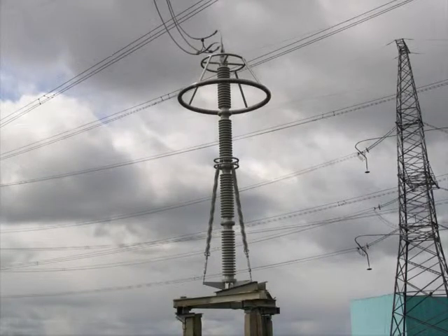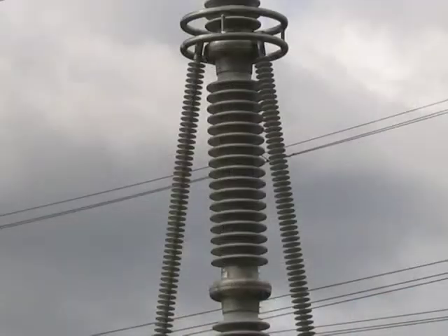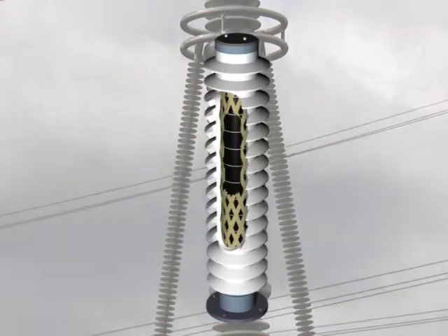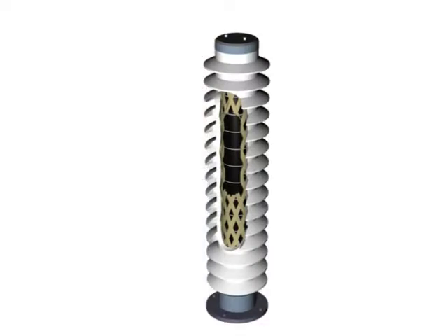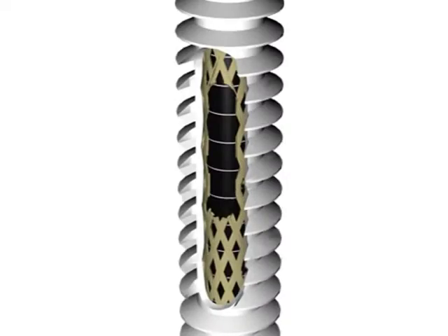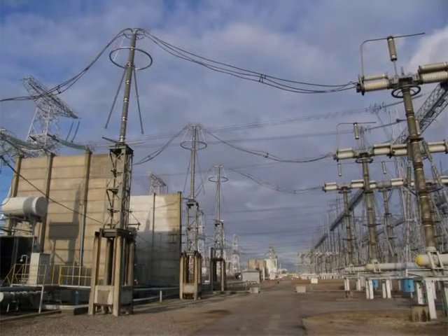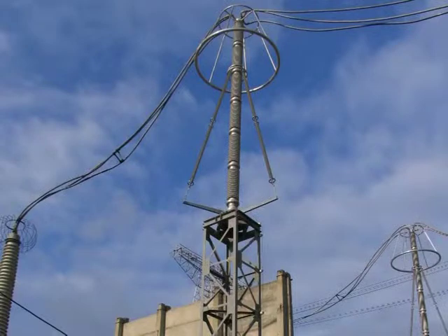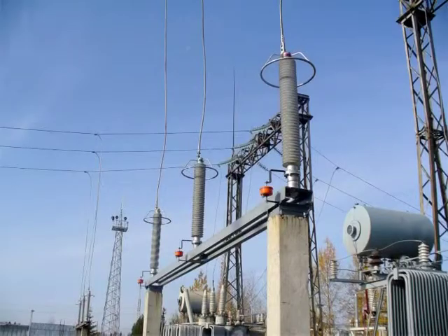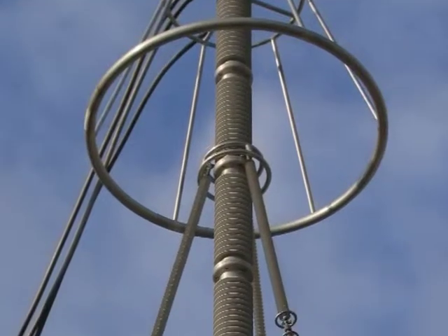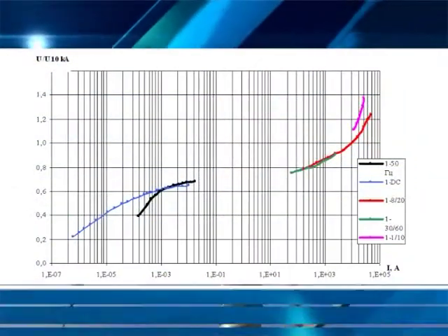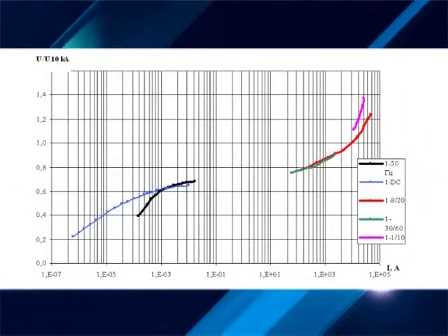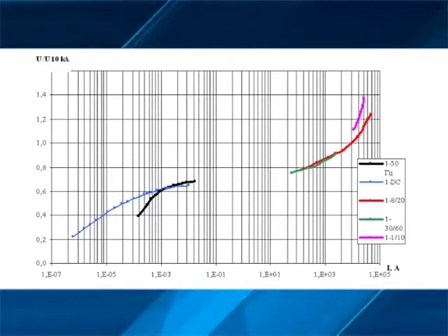Modern surge arresters are the most effective means of protection against overvoltage. A surge arrester is a column of highly nonlinear resistances, varistors, enclosed in a sealed housing. Surge arresters don't contain series-connected spark gaps, which detach the nonlinear resistance from the effects of working voltage, and in normal operating mode, current flows constantly through the varistors of the arrester.